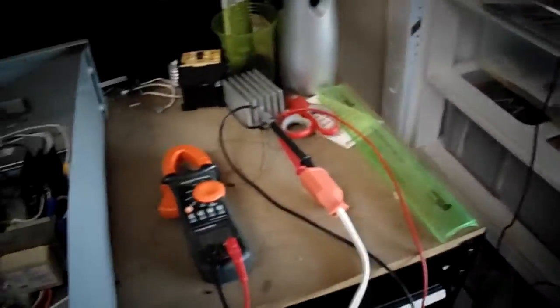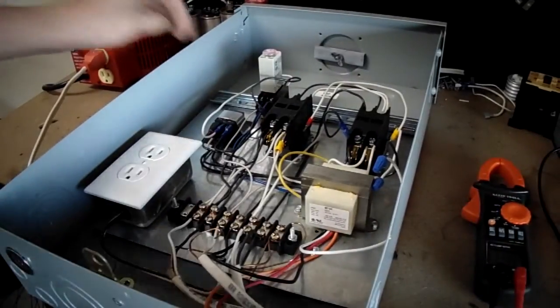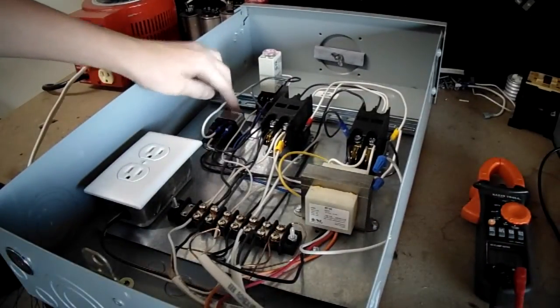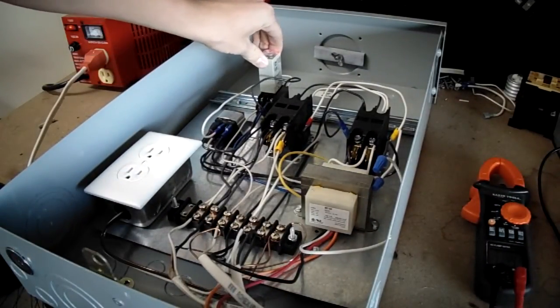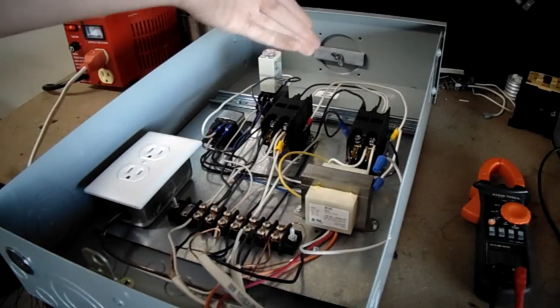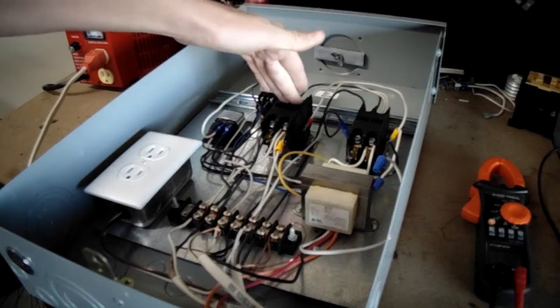It's fairly simple. One relay decides whether to go to source 1 or source 2. That's this one right here. And this one just tells the contactors to wait before switching back to the main source.